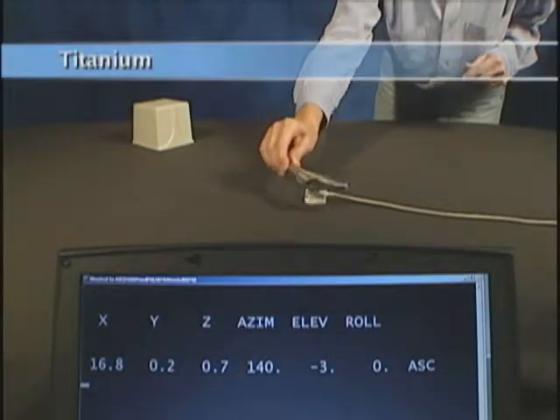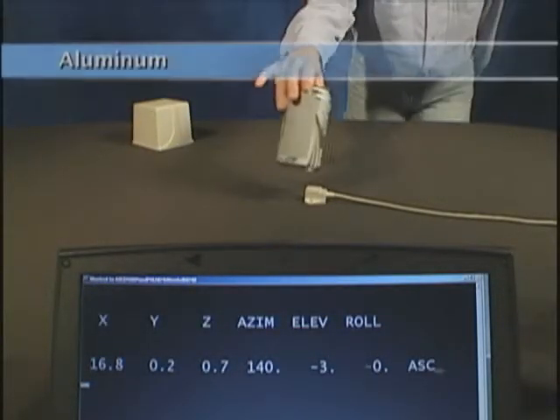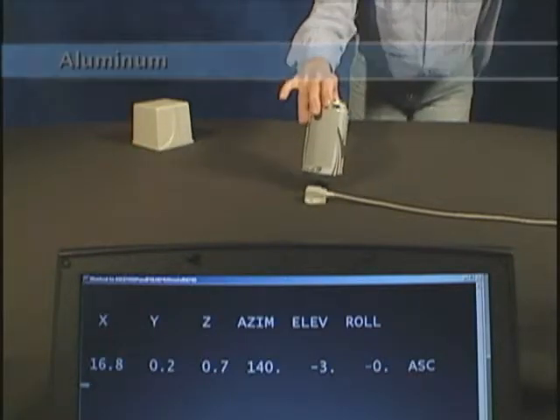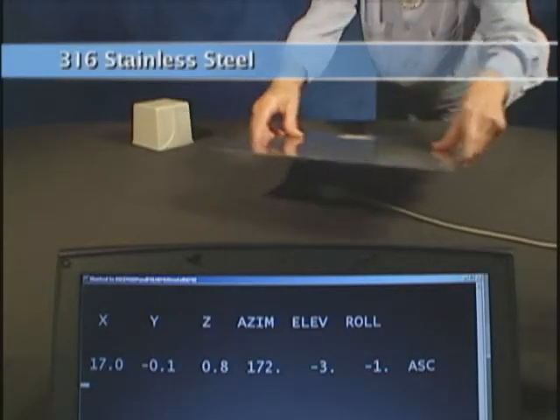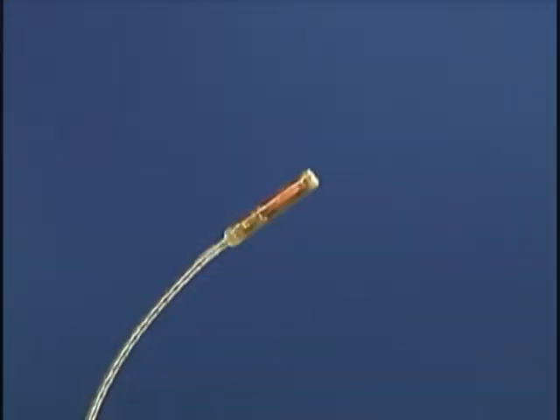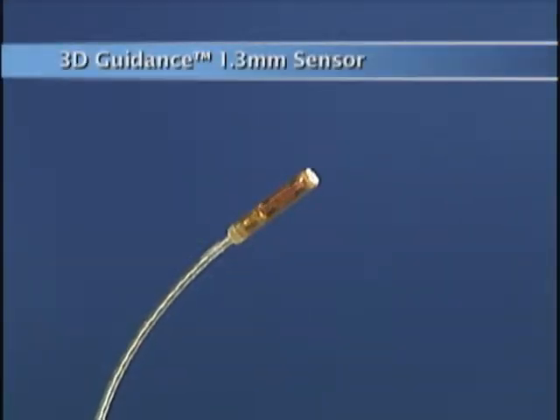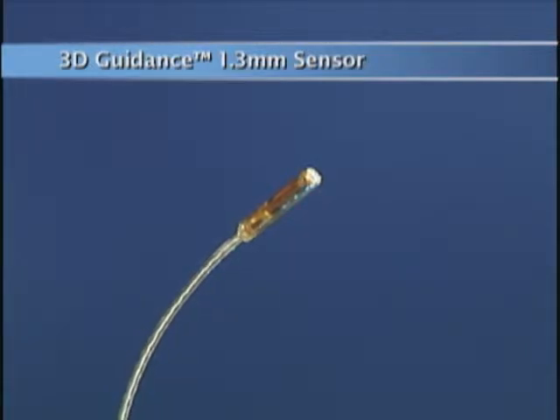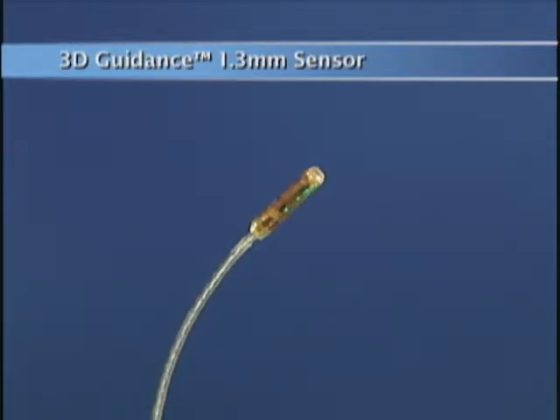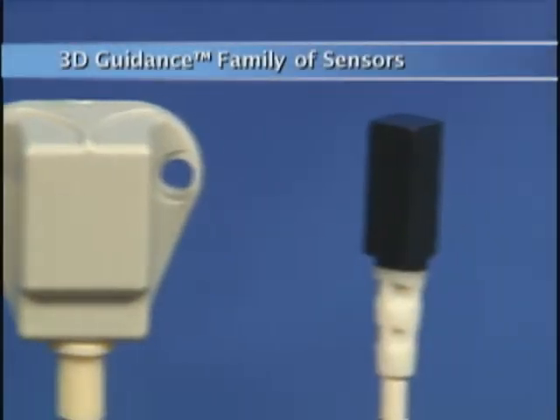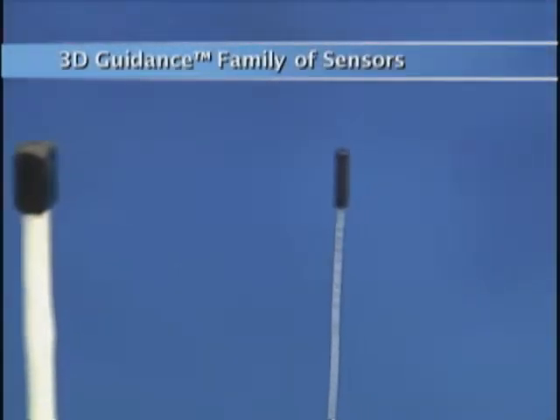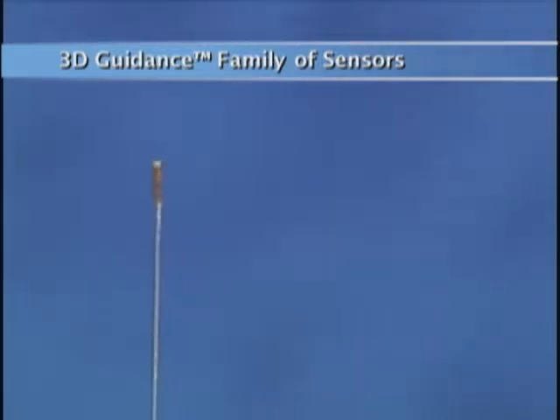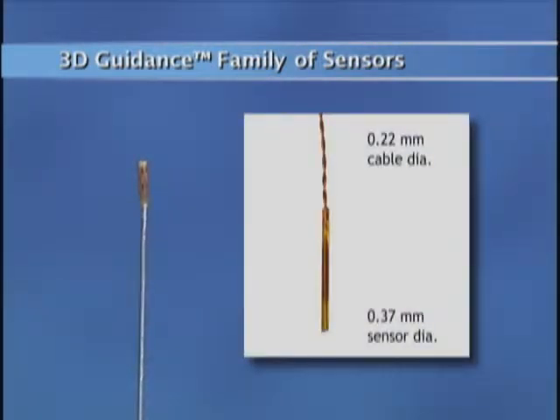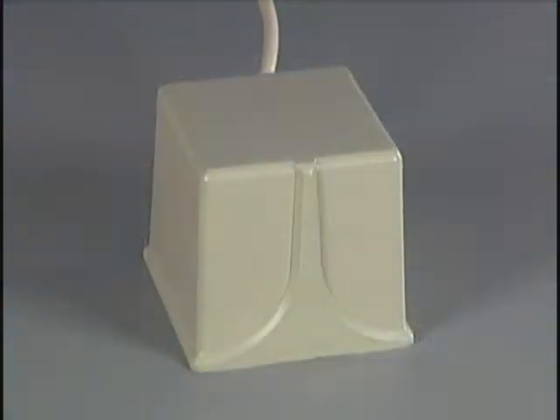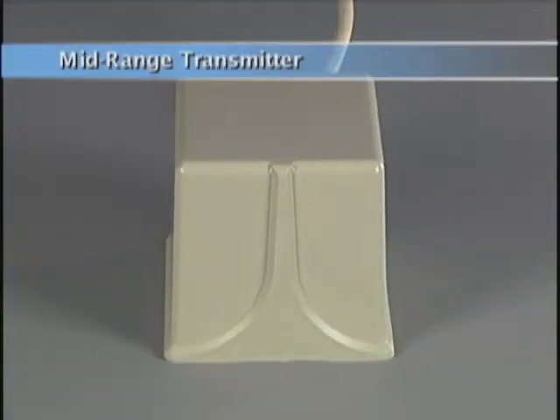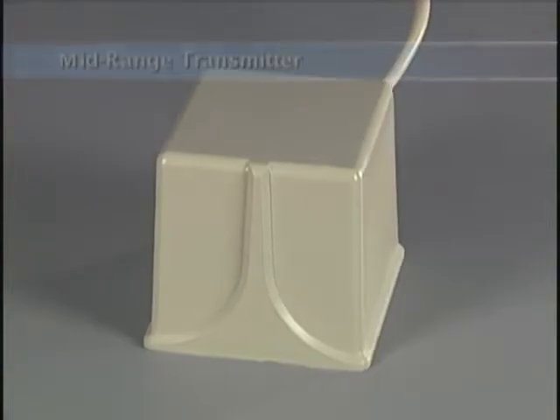DC technology also has the exclusive capability to readily adjust its measurement rate, meaning the system can drive many conductive metal errors to 0. Ascension's latest medical tracker, 3D Guidance, includes micro-miniaturized sensors and transmitters developed specifically for surgical navigation. 3D Guidance sensors are presently 1.3 millimeters in diameter, and 0.3 millimeter sensors are now operational. Transmitter options include the mid-range transmitter for accurate tracking over ranges up to 1 meter.